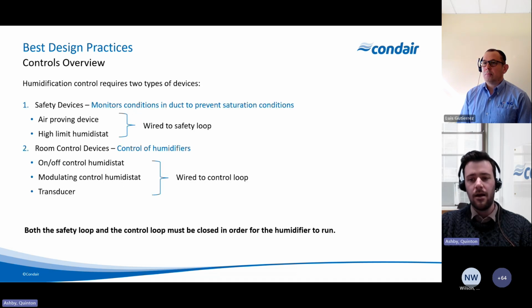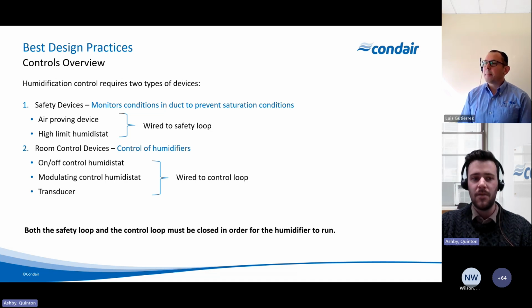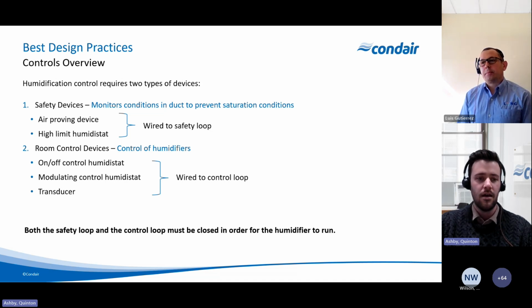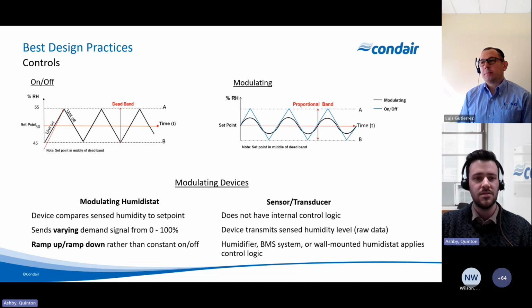Going forward, kind of changing directions a little bit, we're almost out of time, going over controls. There are 2 different types of controls: safety devices and control room devices. It's important to note that air proving device and high-limit humidistats in the duct are necessary. And then I'll go over the other types.